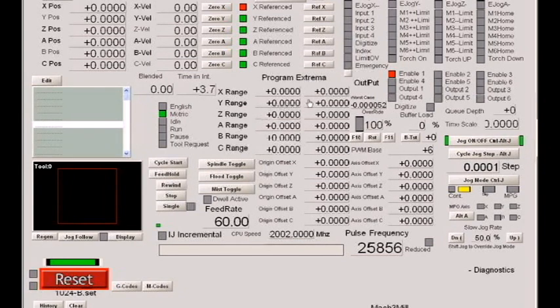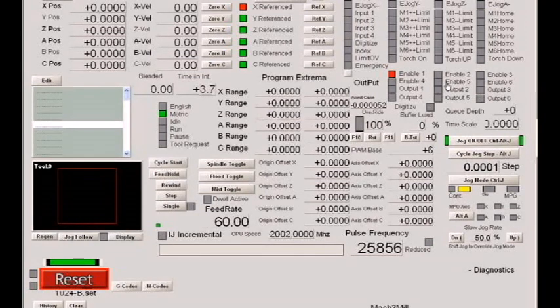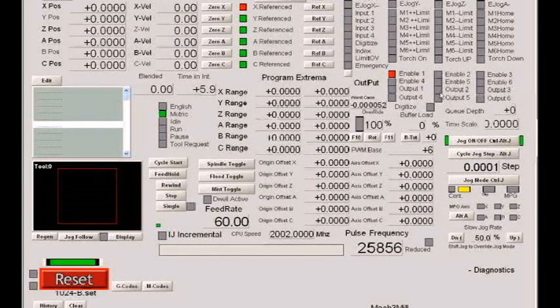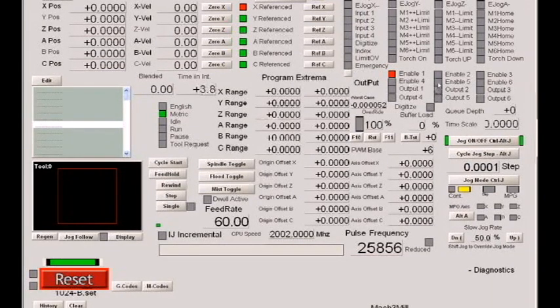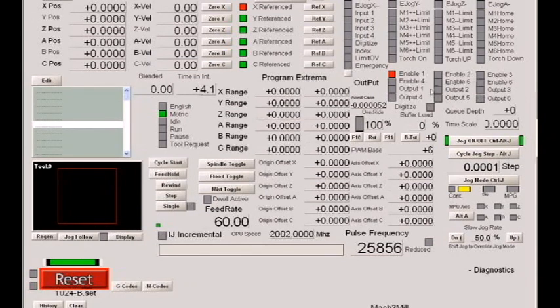You can always tell that because your output is inverted from what its normal logic state should be. When you think it should be on, it's off. When you think it's off, it's on. So when you see that kind of condition, the thing to check immediately is the low active setting for whatever output that you're using.